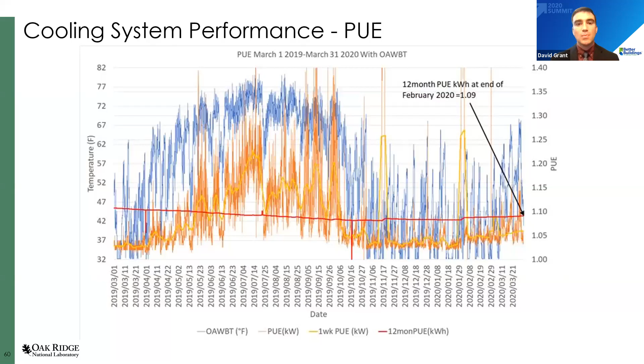So where our savings really came in is the fact that we're water cooling with 70 degrees and using those cooling towers more than our mechanical chiller plants to cool this load. So Summit came in, it can peak at over 11 megawatts, the one system. And so it has really taken over, it's the heavyweight of our data center portfolio right now. And so over the years, we've shifted from that 8 to 10 megawatts of cooling being on the chilled water system to having the 8 to 10 megawatts of cooling on this new system that has the water side economizer. Next slide, please.